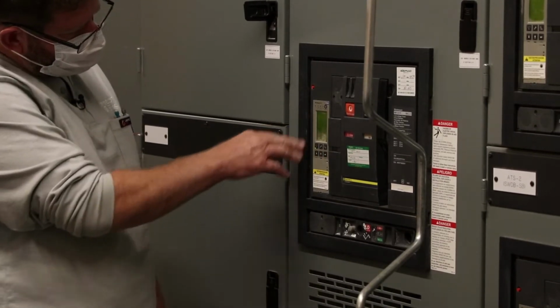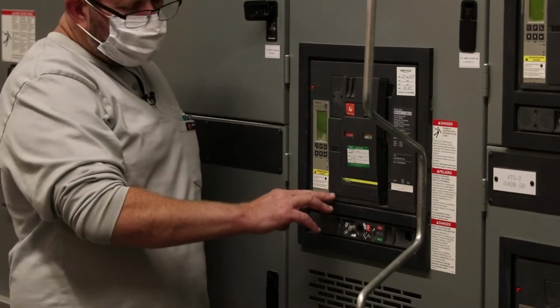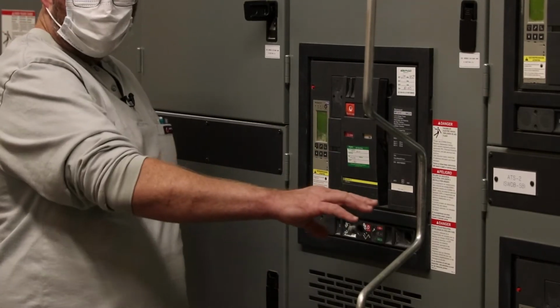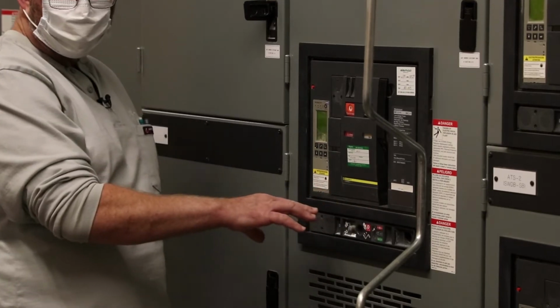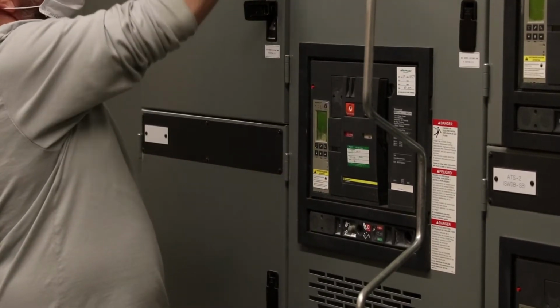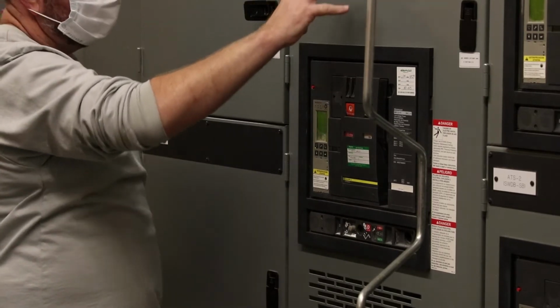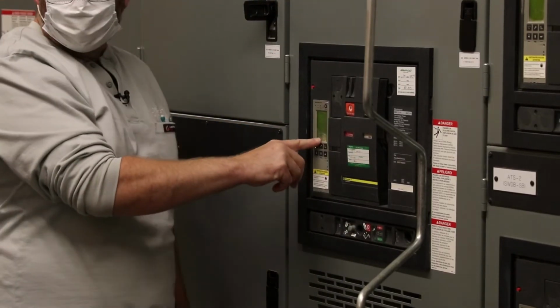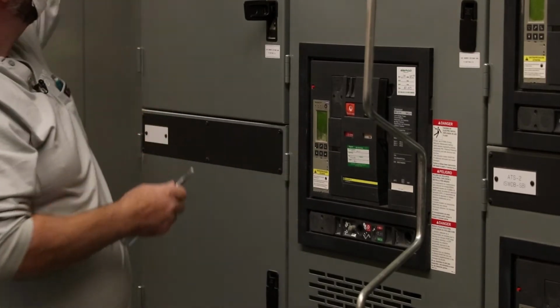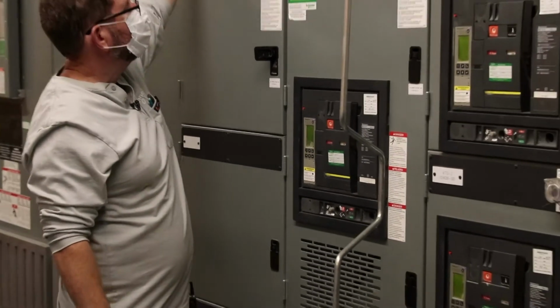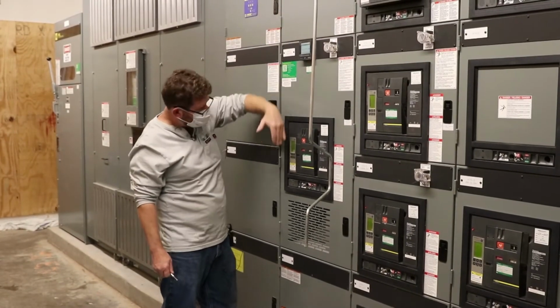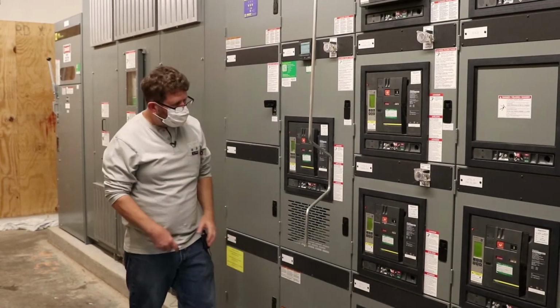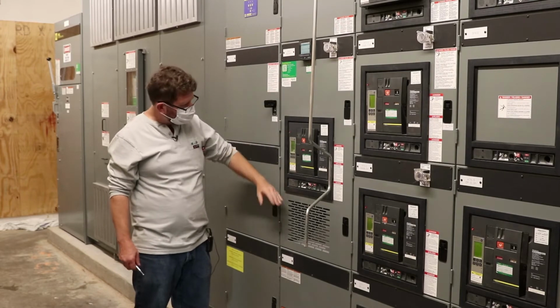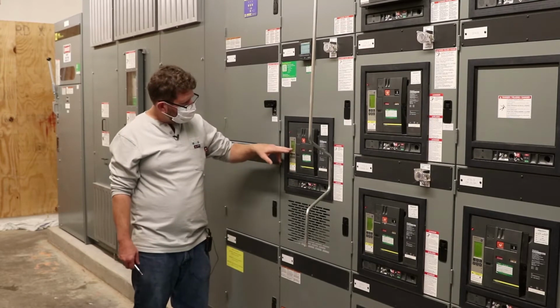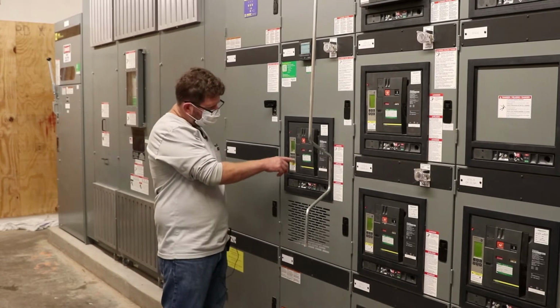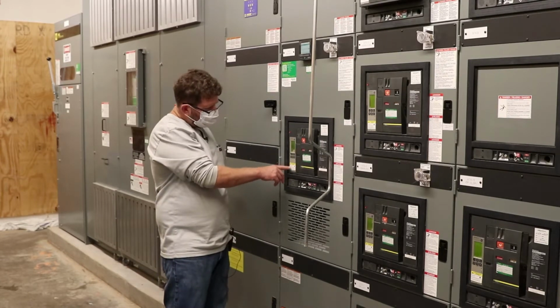Instantaneous voltages. So you got those all there. The voltage indication comes off the bottom of the breaker. It's internal to the breaker, but it's on the bottom of the breaker. So if this switchboard was energized, but the breaker was open, you would not see voltage here. The way the power comes in, you're going to have bus connections up here, going to come over here, down through the breaker, and then out through the rest. So the line side of the breaker is at the top, the load side's down here. These would be de-energized if the breaker's open.